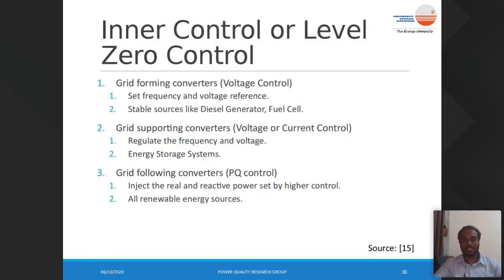So let's see what the inner control, or zero level control, does. Based on this, we have 3 types of converter configuration to operate a microgrid. One is grid forming converters, which are operated in voltage control. Then we have grid supporting converters, which can be operated in either voltage or current control mode. Then we have grid following converters, which are operated in current injection or PQ control mode. We call it PQ control mode.